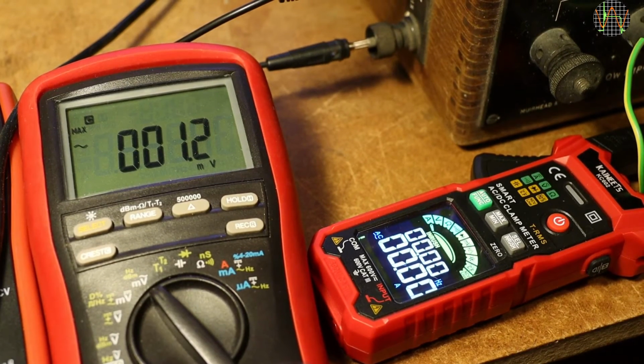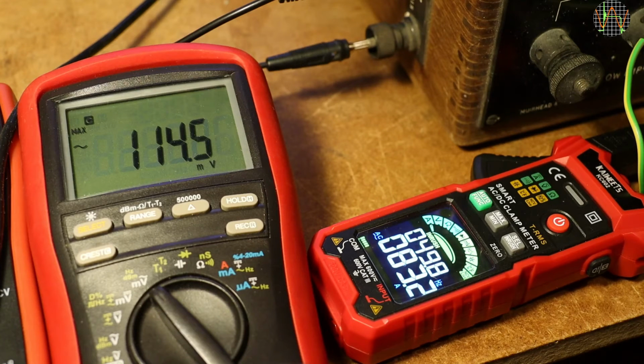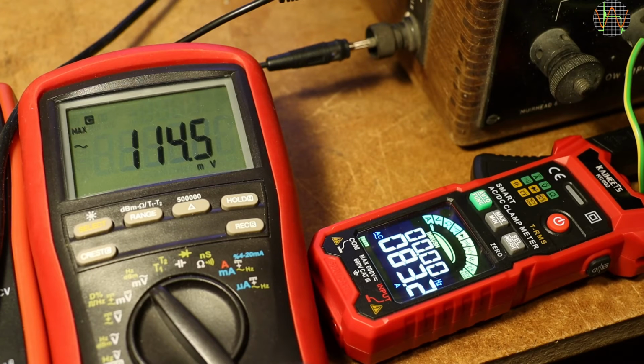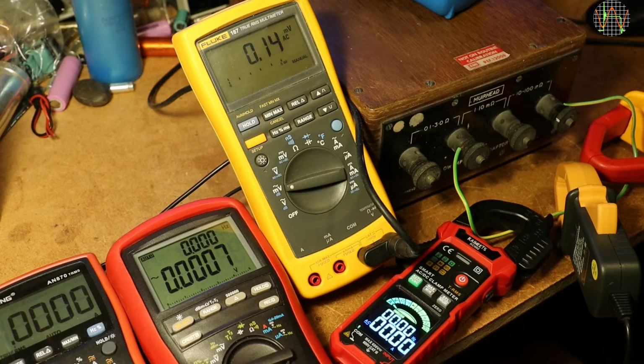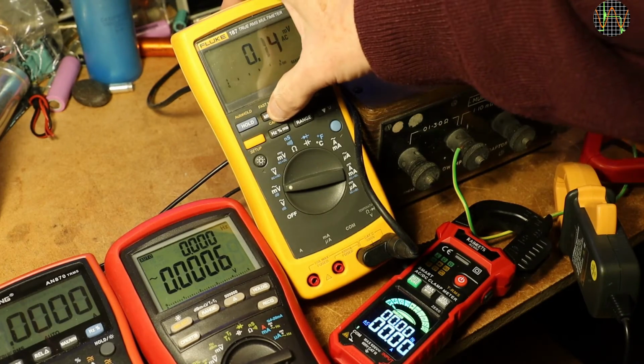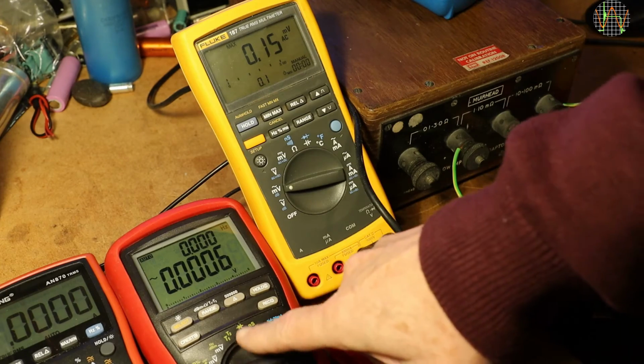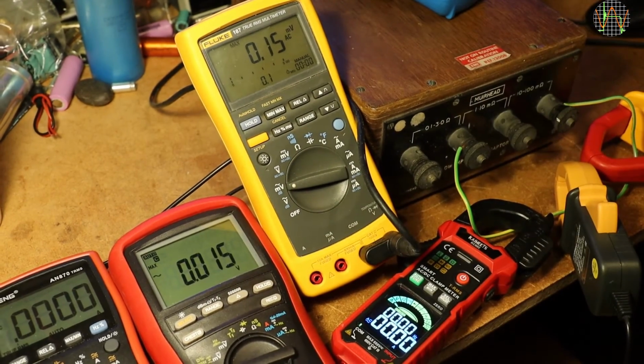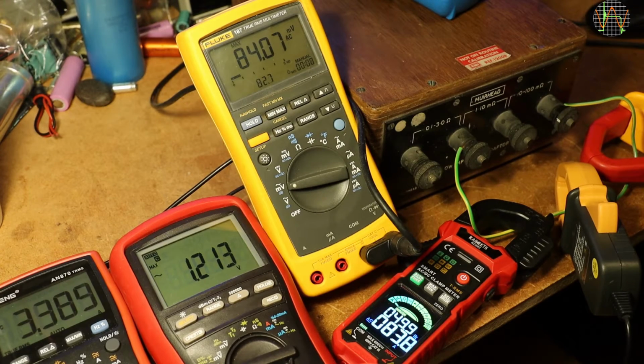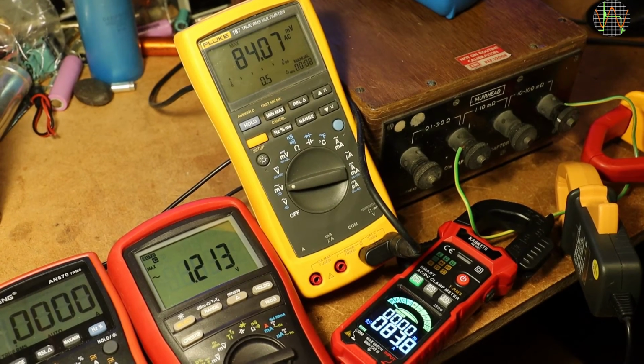I'm using the crest function on the Brymen and inrush on the KC602. Both meters display the highest reading until you reset them. The Brymen reads nearly 115 amps, while the KC602 shows basically the same as before, 83 amps. That discrepancy kind of worried me. To explore this further, I expanded the setup with another current clamp and my Fluke 187. To rule out that the Fluke i1010 current clamp had anything to do with the discrepancy, I moved it to the Fluke 187 and used a different clamp which does 10 millivolts per amp on the Brymen. The Fluke has two modes, normal min-max and fast min-max, which is more like the crest mode of the Brymen. Trying the normal min-max first, the Brymen crest mode registered 121 amps with the other clamp, while the Fluke is in line with the KC602.